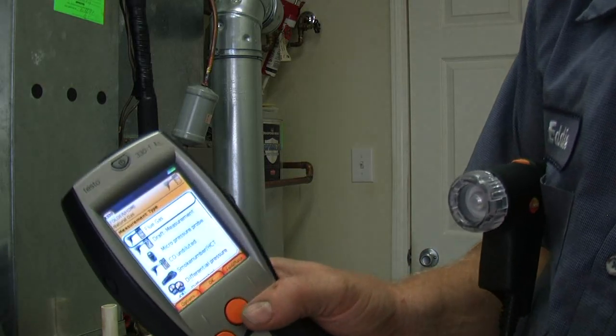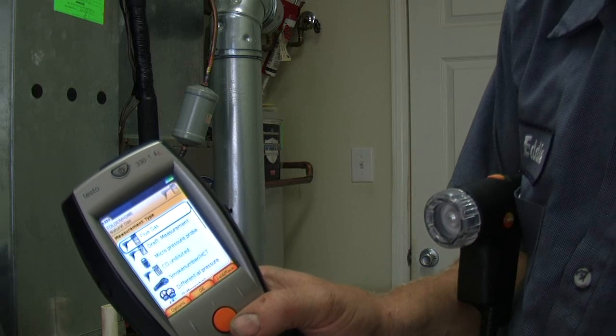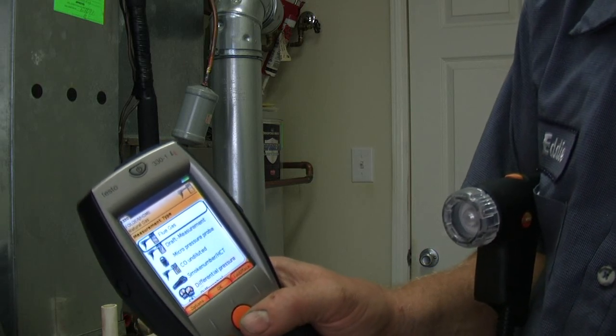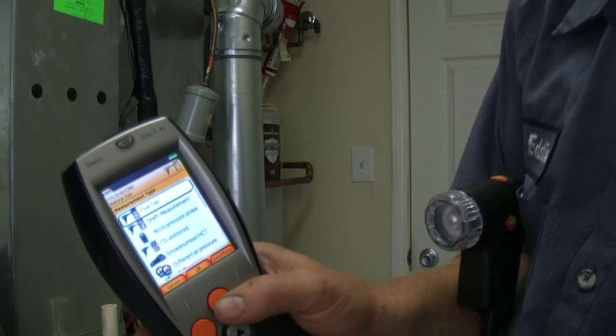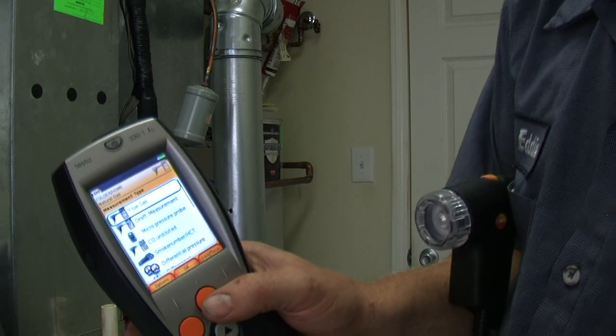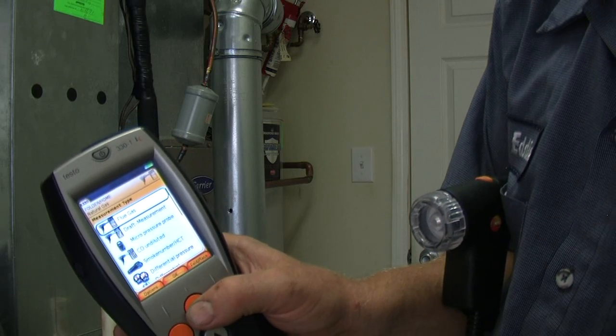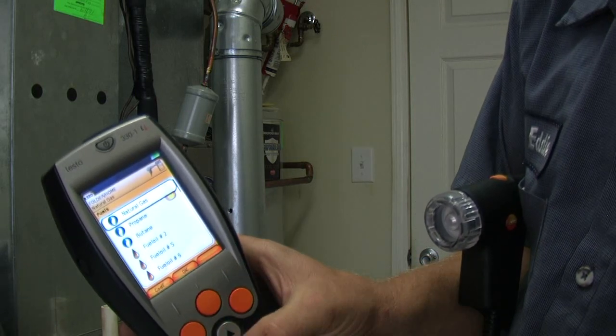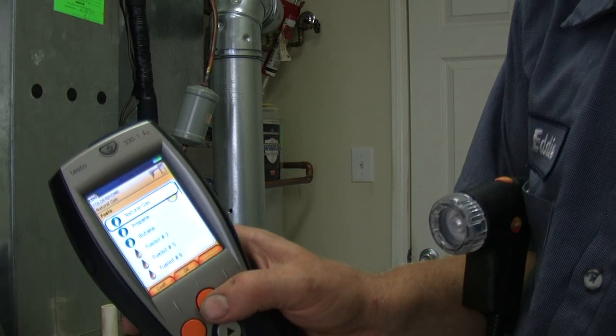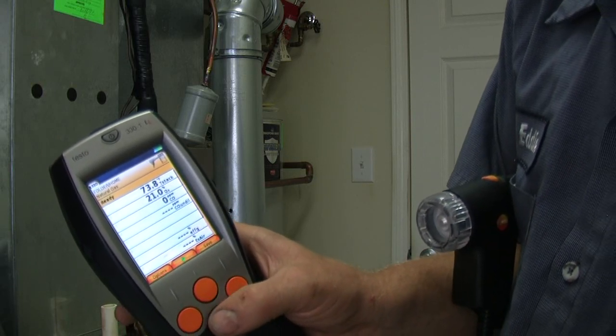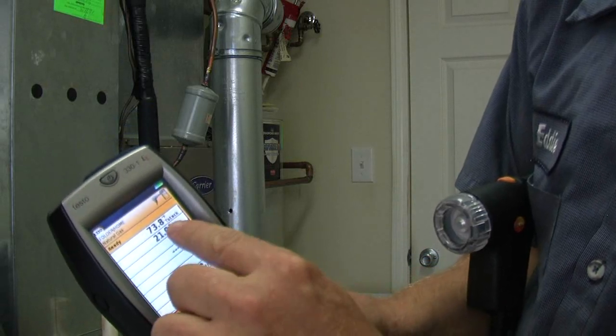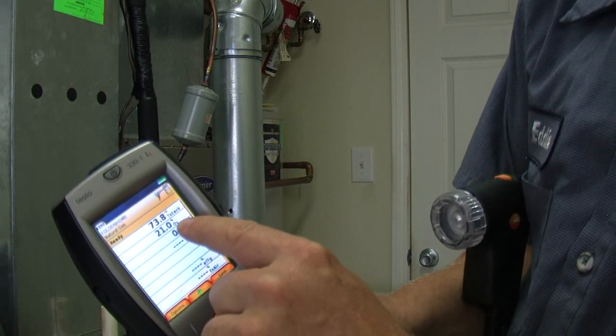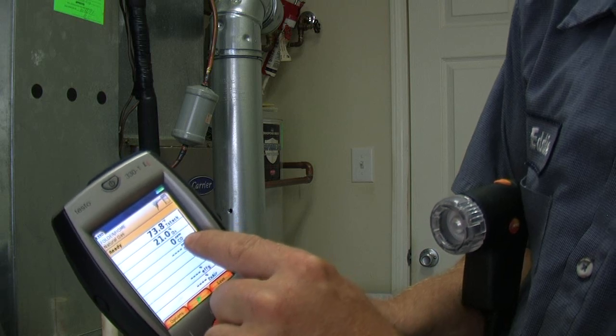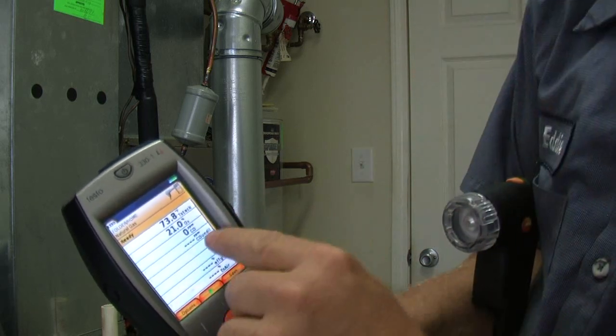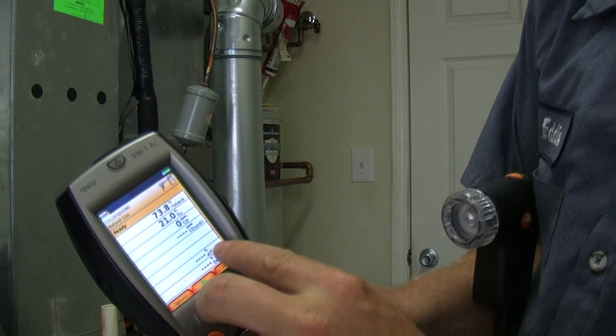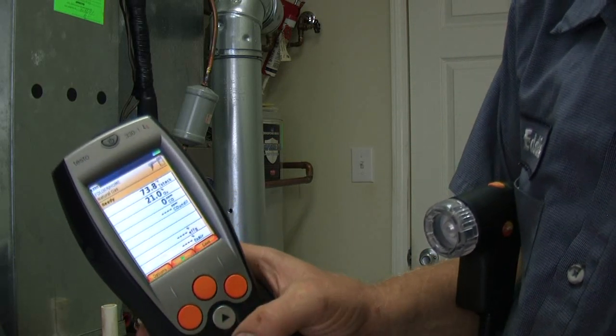Alright, very first thing I'm going to do is go ahead and do a flue gas test. And I'm going to do that because I want to check the heat exchanger. And this is how I check a heat exchanger to see if there's any leaks. So I'm going to go ahead and hit OK. You're going to select whatever gas you're using. We're using natural gas here. Alright, and this is the screen that's going to show up. It's going to show you the stack temperature. It's going to show you your O2, oxygen. It's going to show you your carbon monoxide and undiluted carbon monoxide. It's going to show you what efficiency it's running at.